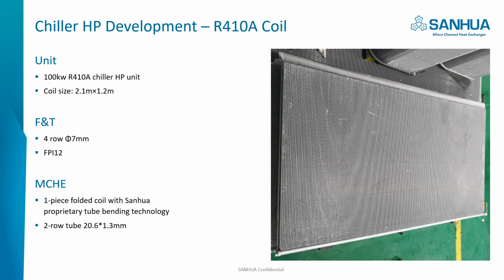With the renewed technology, we designed for chiller heat pump units. This is a unit of 100 kilowatts chiller heat pump using R410A refrigerant, and the coil size is 2.1 meters long and 1.2 meters high. The baseline fin tube heat exchanger is 4-row 7 millimeter, and the fin density is 12 fins per inch. For microchannel, we use a one-piece folded coil with SANHUA proprietary tube bending technology, and it uses 2-row 20.6 millimeter tubes. The tube height is 1.3 millimeters.